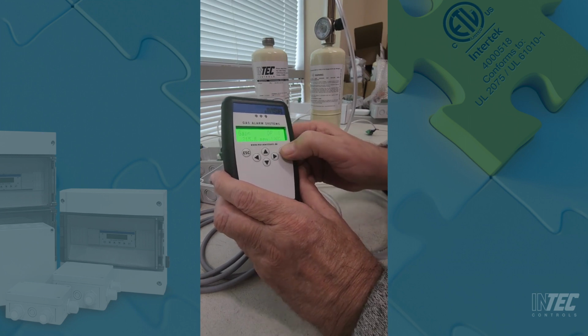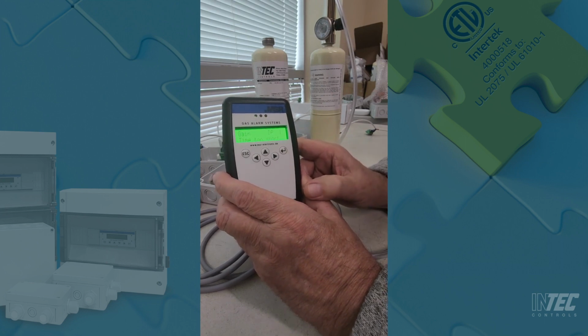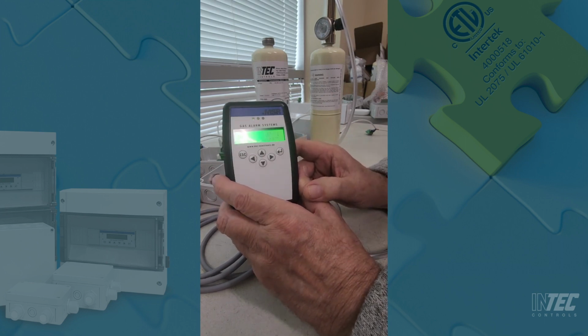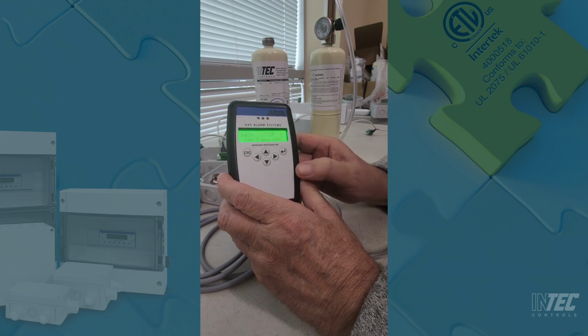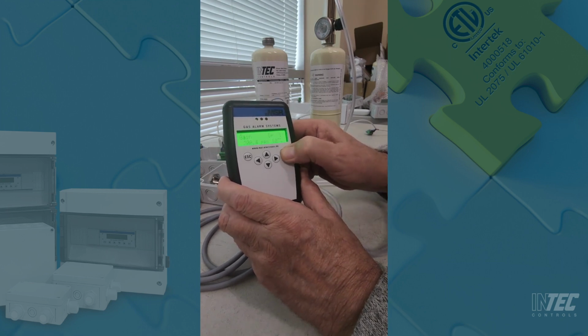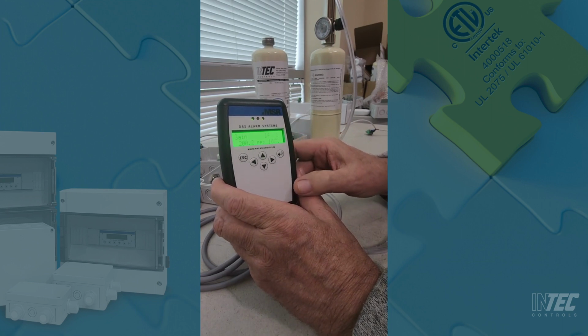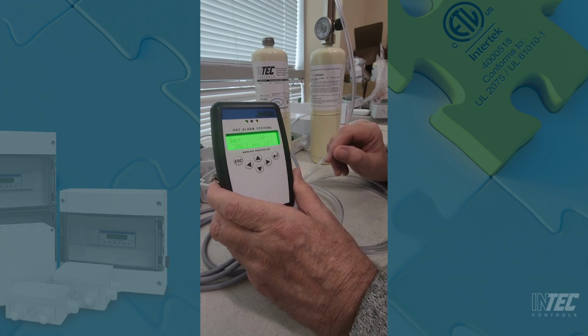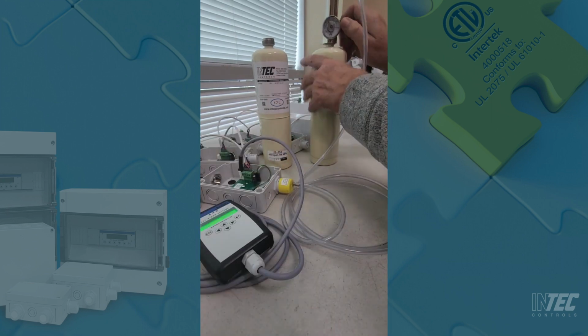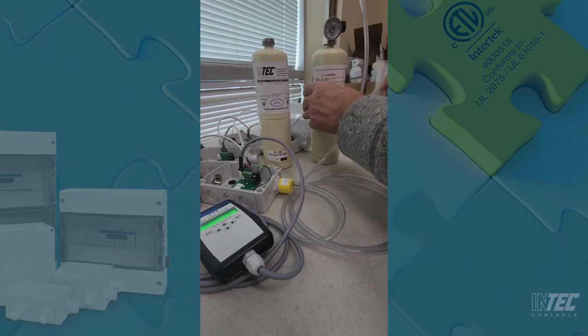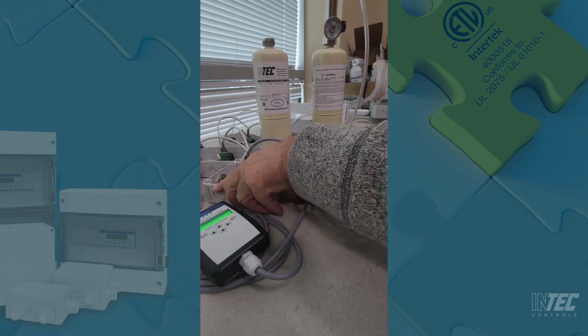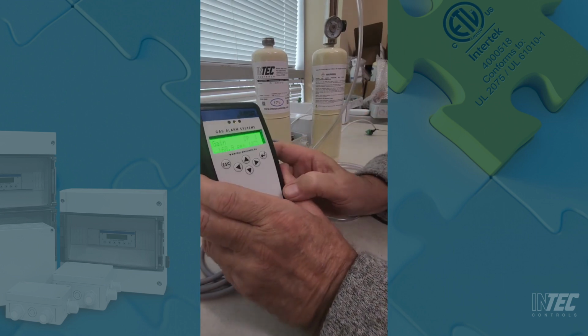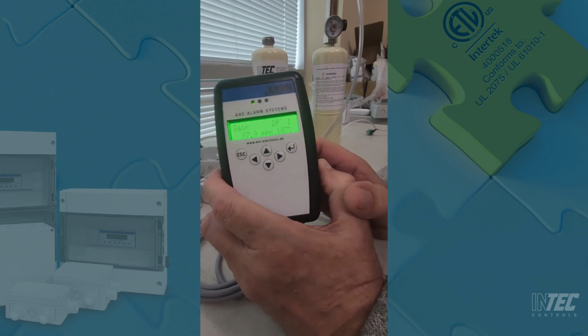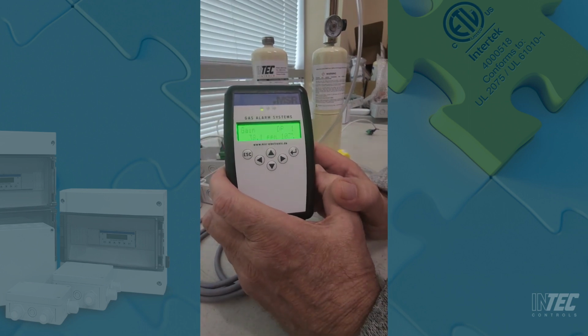Now we're going to go ahead and hit enter. It'll say time too short. Just let it say. And you can see the value on the screen drop to 190/200. Then hit the enter button to save. And you're calibrated. At this time, you turn off your gas and remove the cup from the sensor head. You can see the value of the sensor dropping after you remove the gas.